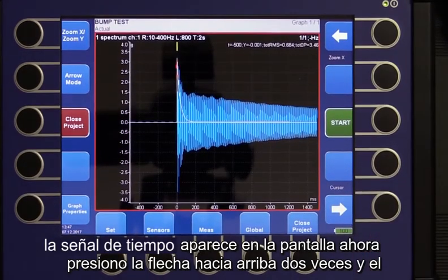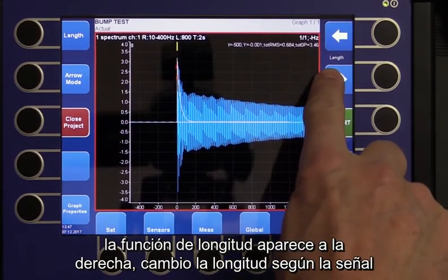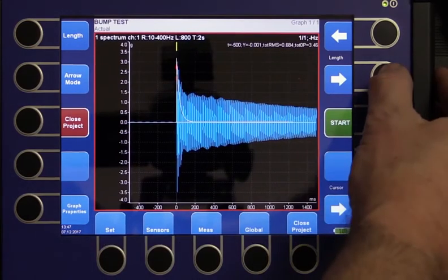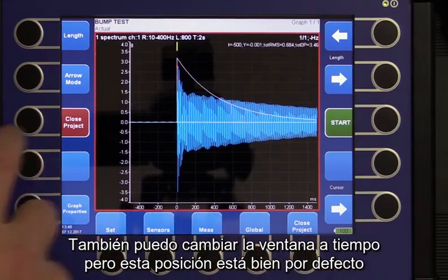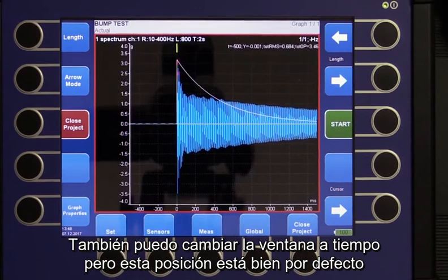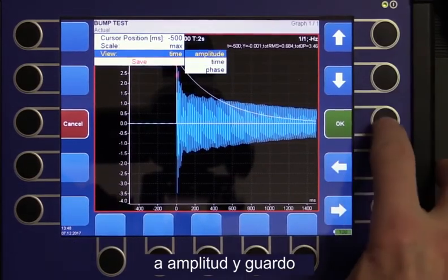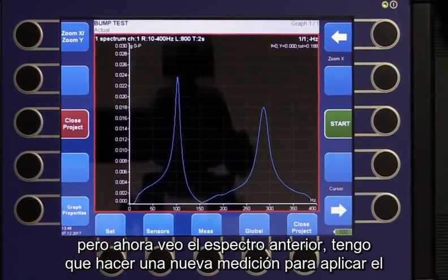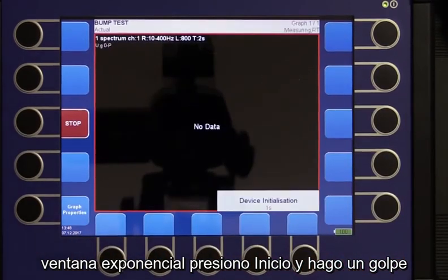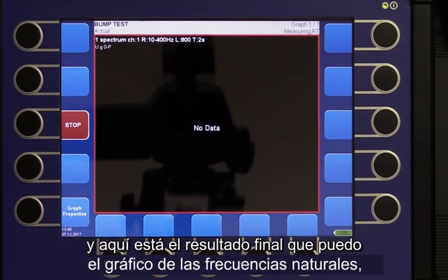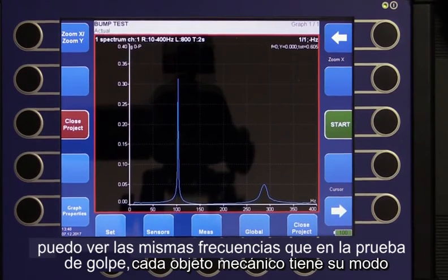The time signal appears on the screen. I press the up arrow twice and the Length function appears on the right. I change the length according to the signal. I can also shift the window in time, but this position is fine — the default position is at the trigger position. I press Graph Properties, set the view back to Amplitude, and save. Since the old spectrum is still displayed, I press Start and make a hit to apply the exponential window. Here is the final result: the graph with natural frequencies. I can see the same frequencies as in the bump test.